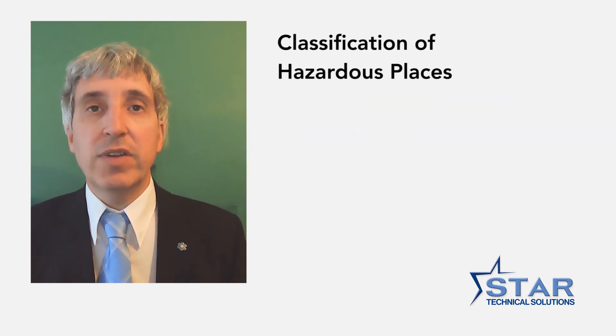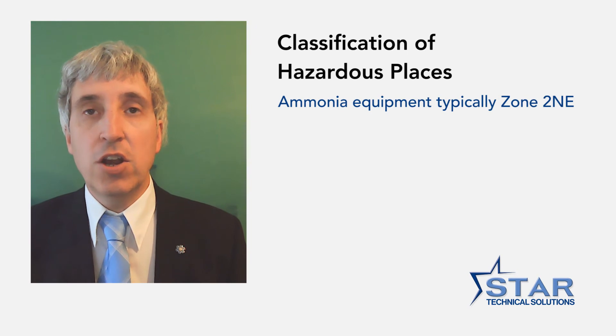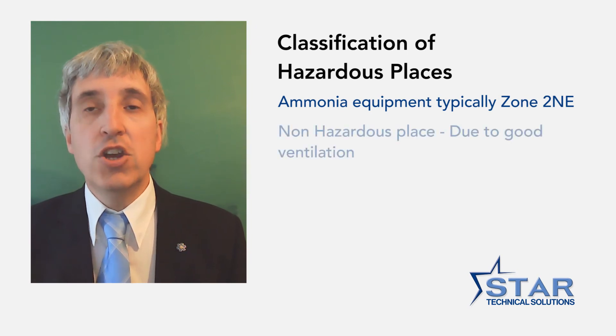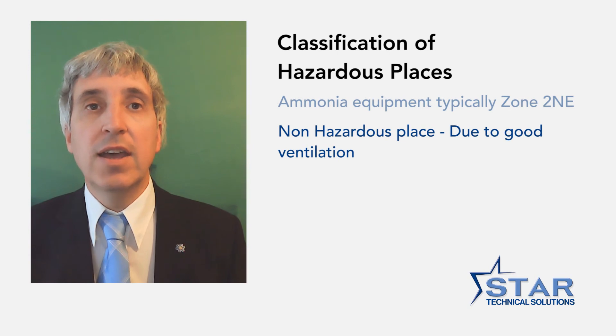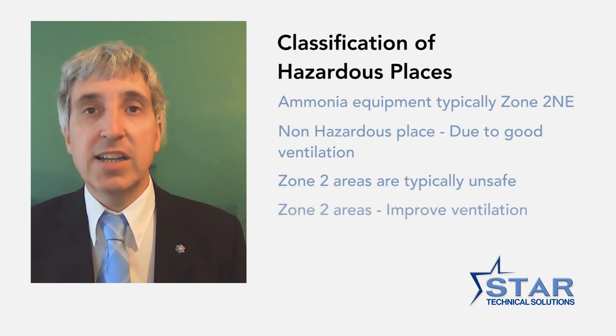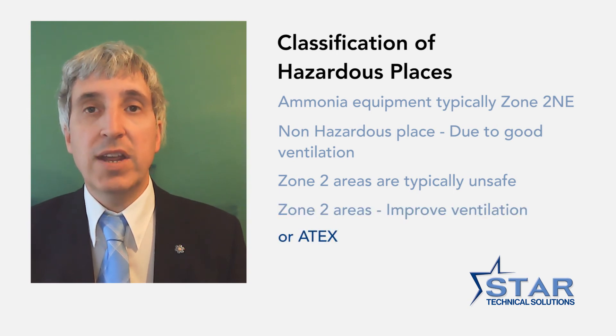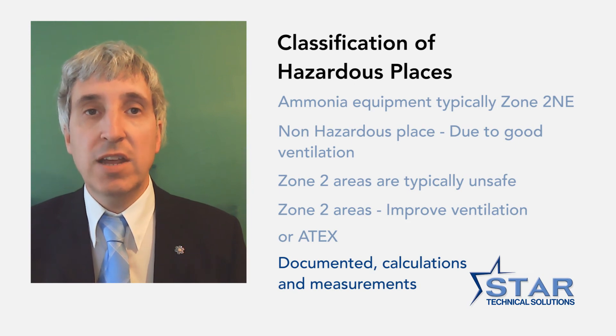When carrying out a classification of hazardous places, ammonia equipment locations are typically designated as Zone 2NE non-hazardous areas due to having good ventilation. However, often during our inspections we identify areas as Zone 2 hazardous areas. These Zone 2 hazardous areas are deemed as unsafe and typically require the ventilation to be locally improved. Normally, places classified as Zone 2 should have ATEX equipment, which is very expensive. When carrying out a classification of hazardous places, the classification method must be documented, which includes the calculations and measurements.